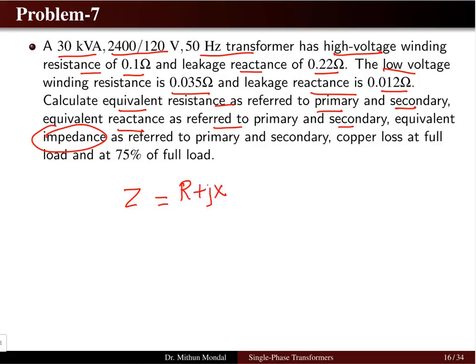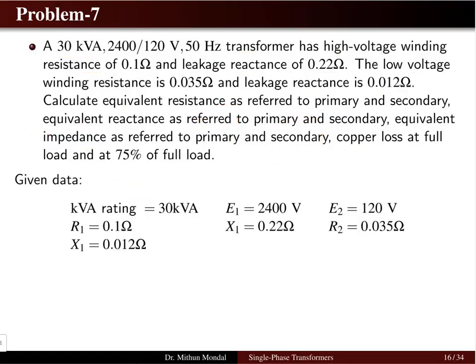So we have to determine the total resistance, total reactance, and the total impedance both from the primary side and the secondary side. We have to determine the copper loss also at the full load condition and 75% of the full load condition. So all the data that are given to us, let us first note down.